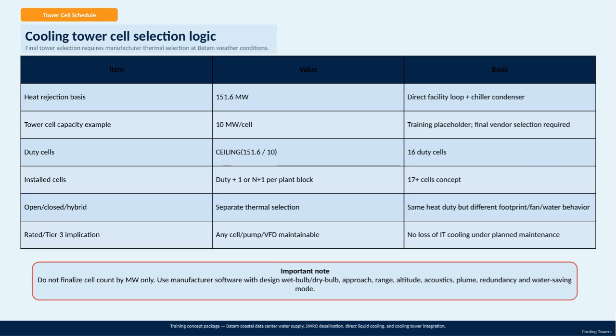The final tower selection isn't just about meeting a heat load number. It requires a detailed thermal selection process conducted by the manufacturer, specifically tailored for Batam's weather conditions. This ensures that the tower performs efficiently in the local climate. The training concept package we're using covers Batam's coastal data center water supply, SWRO desalination, direct liquid cooling, and integration with the cooling towers. It's a comprehensive approach designed for optimal performance.